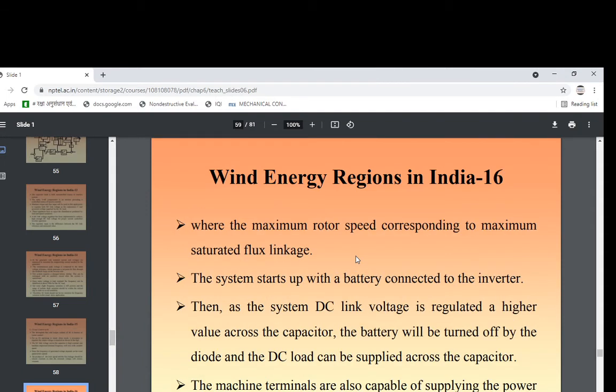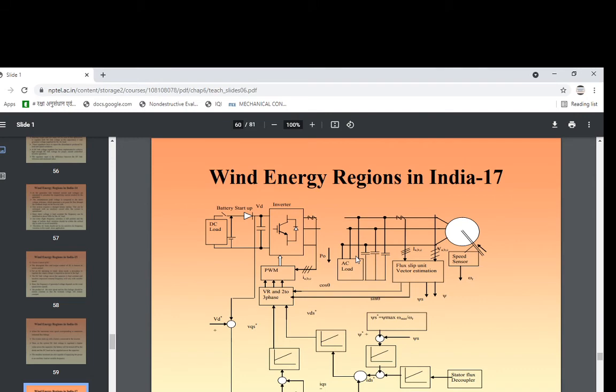The maximum rotor speed corresponds to the maximum saturated flux linkage. The system starts up with the battery connected to the inverter. Then, as the system DC link voltage is regulated at a higher value across the capacitor, the battery will be turned off by the diode and the DC load can be supplied across the capacitor. The machine's terminals are also capable of supplying power to an auxiliary load at variable frequency. This is the wind energy regions in India.